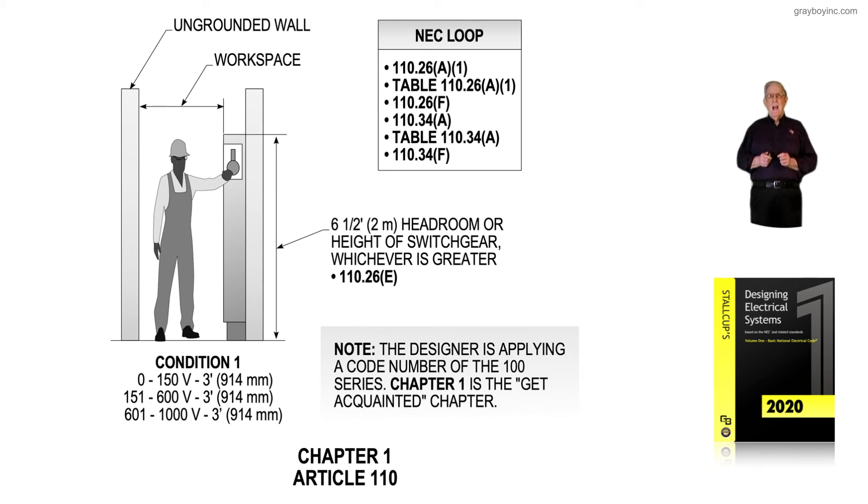If you get into higher voltages — over 1,000 volts — then 110.34A and Table 110.34A, along with 110.34(F), deals with the clearances in and around high voltage systems. In the OSHA standards, it's still categorized as less than 50, 50 to 600, and over 600 volts. My understanding is that when OSHA updates OSHA 1910 Subpart S, the voltage threshold of over 600 volts may change to over 1,000 volts. Keep that in mind — Article 110 gives the basic clearance rules in and around equipment.